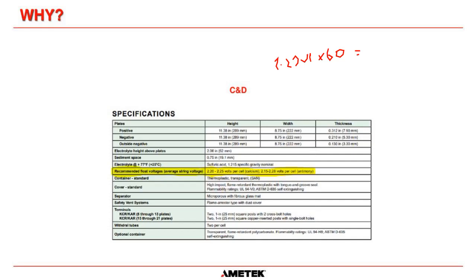2.23 times 60 is equal to 133.8. So that is what you should set your charger at. But when you go and do your maintenance, you should be taking individual cell voltages. And if your cell voltage either drops below 2.2 volts per cell or goes above 2.25 volts per cell, that is when you need to do an equalize.